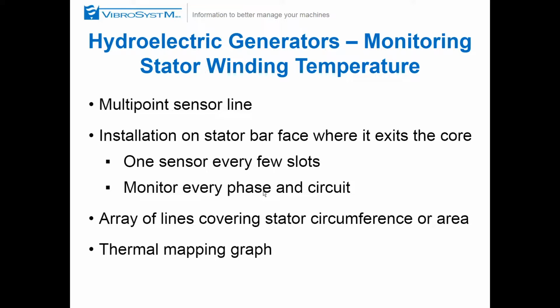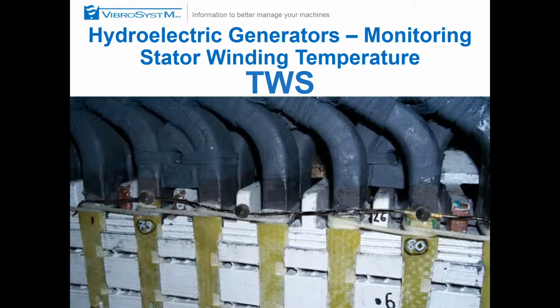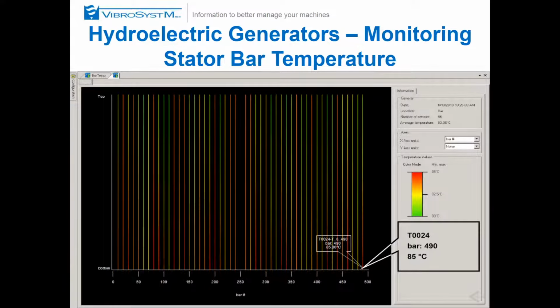On the left, don't get excited, that's not the price, that's just to give you an indication of the size. And it's a multi-point sensor line. As I said, you can go up to 100 sensors and you can install it just about everywhere. And it's digital, so there's no calibration, there's no adjustment. You just hook it up to the interface and you can measure the temperature as the unit operates. You have some examples here on stator windings and on press fingers. And it gives you this type of graphic, 1 per sensor.